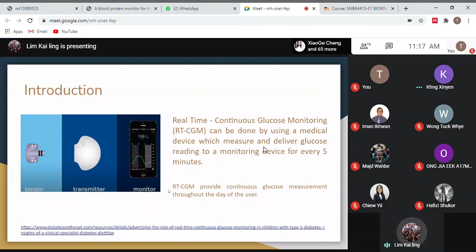Continuous glucose monitoring can be done by using this medical device shown in this figure, which consists of three main parts, including a sensor, transmitter, and a monitor. This device is able to measure and deliver the glucose reading to a monitoring device every 5 minutes, which means that it can provide a continuous glucose measurement throughout the day of the user.